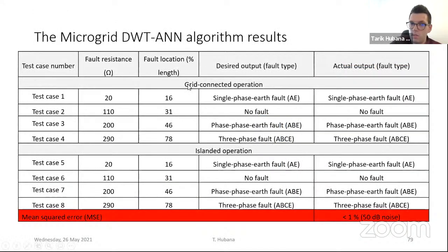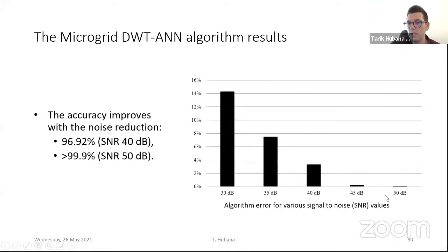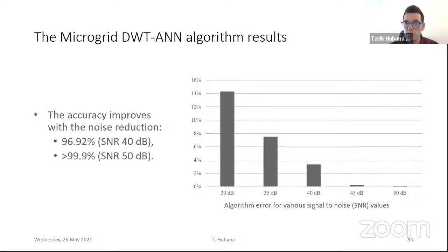These simulation scenarios showed great accuracy with different fault resistances, fault locations, and different fault types, with the mean squared error less than 1% for the 50 decibel noise. Of course, with the increase of the noise, the accuracy decreases.